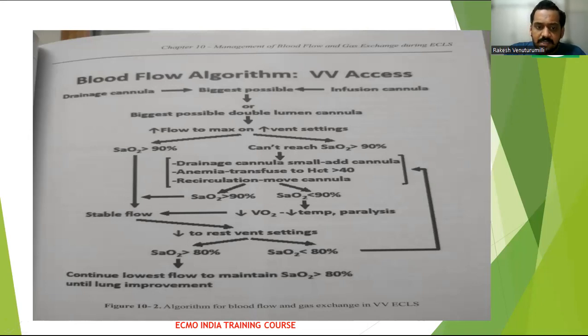After decreasing the rest settings and stabilizing the flow, if the saturation is more than 80, try to maintain it with the least possible flows until the lung improves. Okay. Once you're increasing the flows to the maximum and you're unable to reach a saturation of more than 90, that means that your flow is inadequate. So try to add one more drainage cannula.